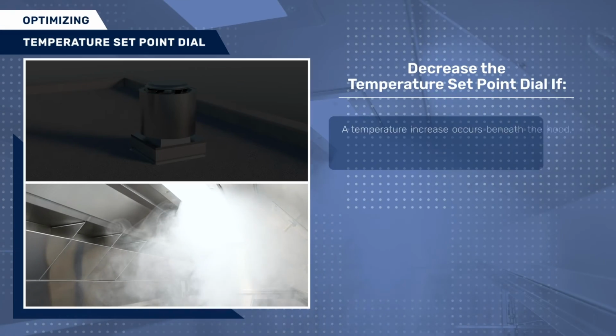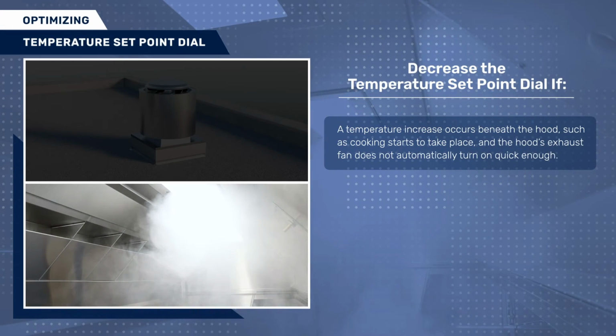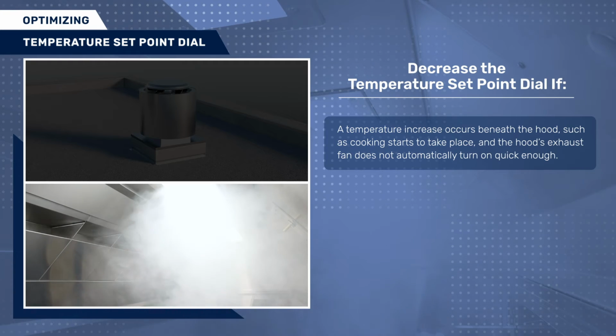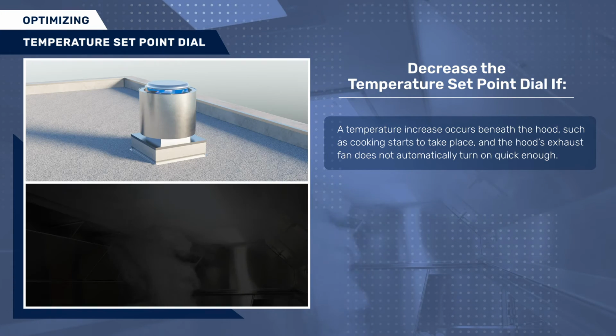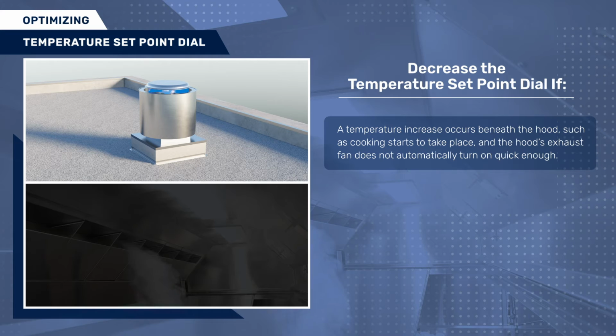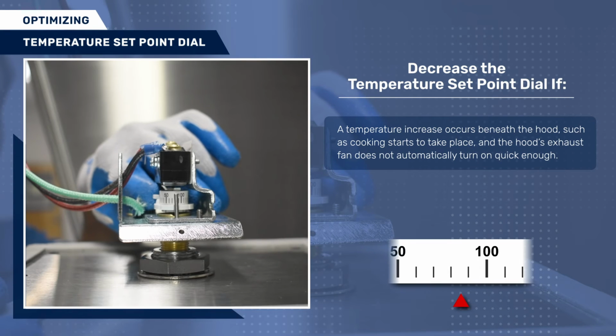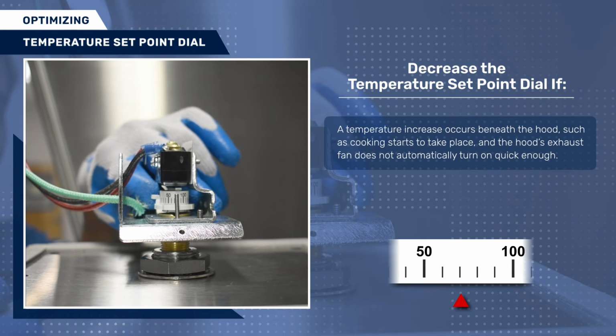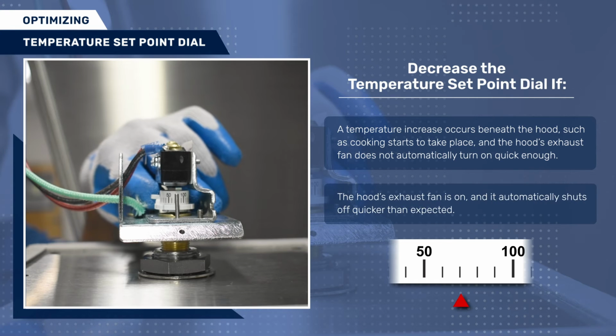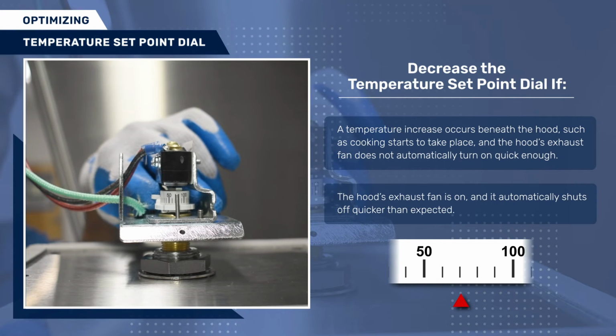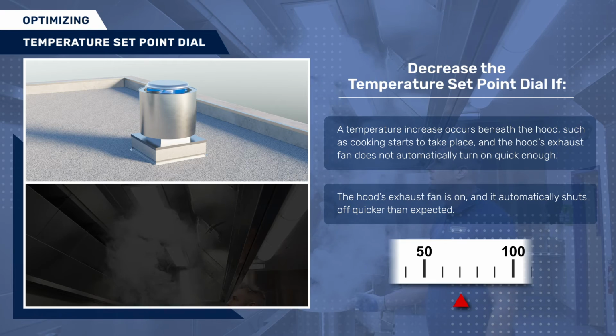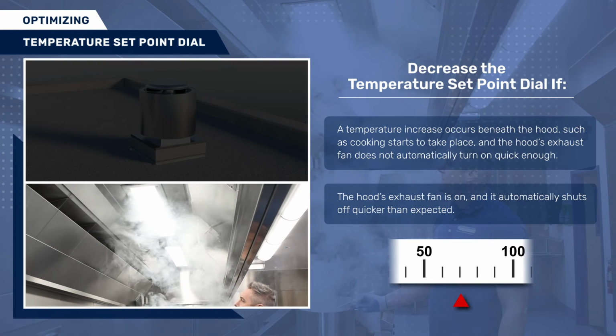If you run into a scenario where a temperature increase occurs beneath the hood, such as cooking starts to take place, and the hood's exhaust fan does not automatically turn on quick enough, then decrease the temperature set point to a level that meets the demand of your kitchen. You may also need to decrease the temperature set point in situations where the hood's exhaust fan is on, and it automatically shuts off quicker than expected.